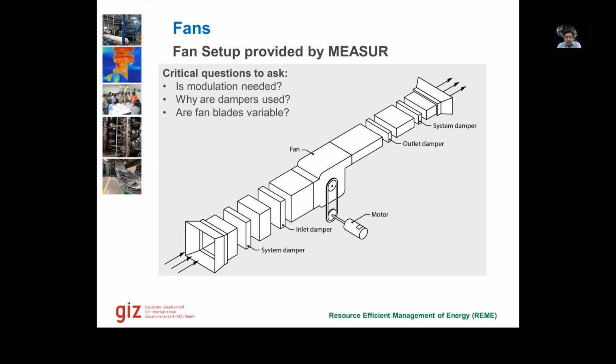Then we come to fans. This is a typical fan duct system provided by MEASUR, where we have fan input, then multiple dampers, the fan and the motor, and then dampers at the outlet as well. So the question is, is modulation required, or is it a continuous flow system? If modulation is required, are we using dampers or variable frequency drives? There are some industrial fans whose blades also have variable angles. You can set the blade angle as well.